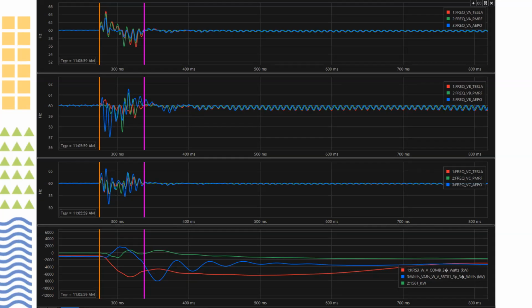Up here is A phase from 3 different sites. B phase from 3 different sites, and C phase from the same 3 different sites. We're seeing different frequencies per phase from 3 different sites in a short time frame. We don't know what's causing this, to be honest, but it's just something that is getting picked up. We don't know if it's an error in the CCVTs during the transient time interval.